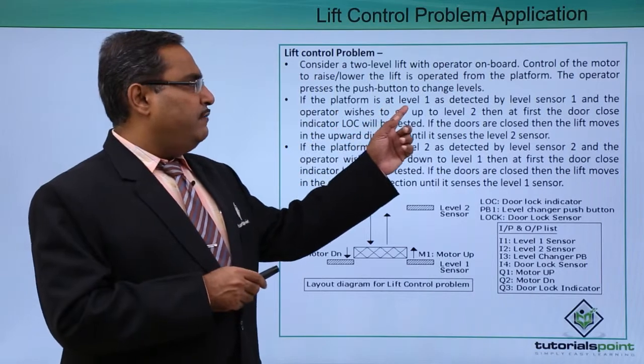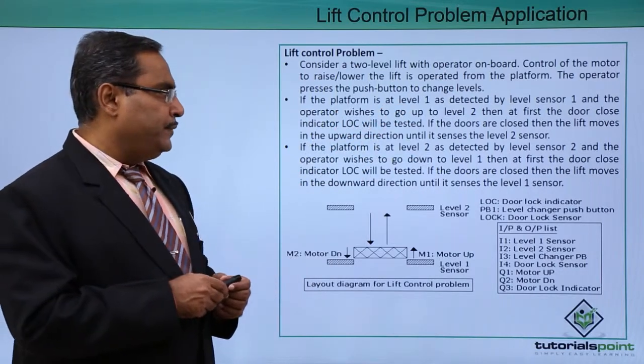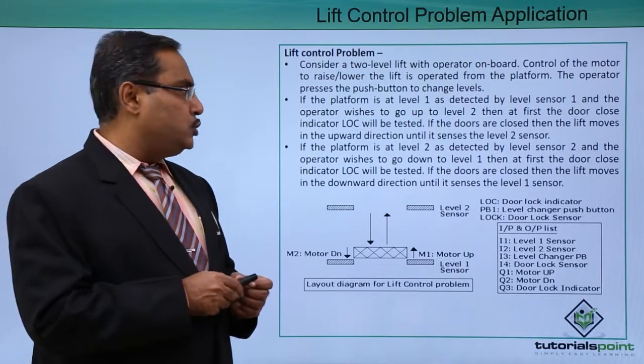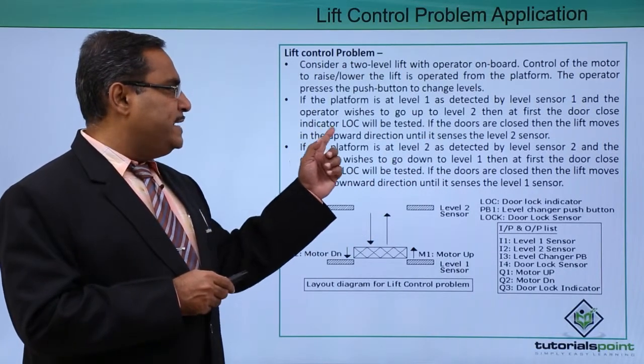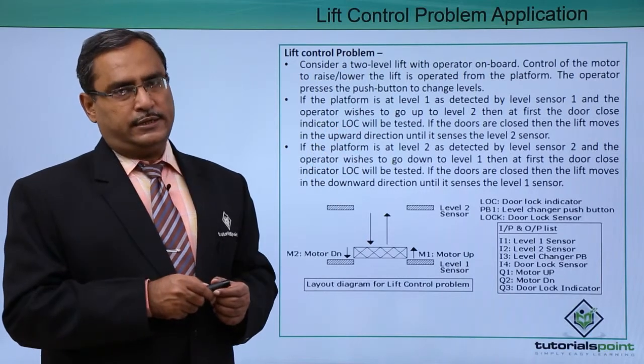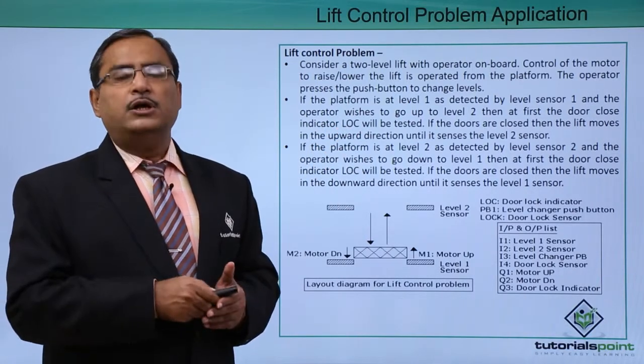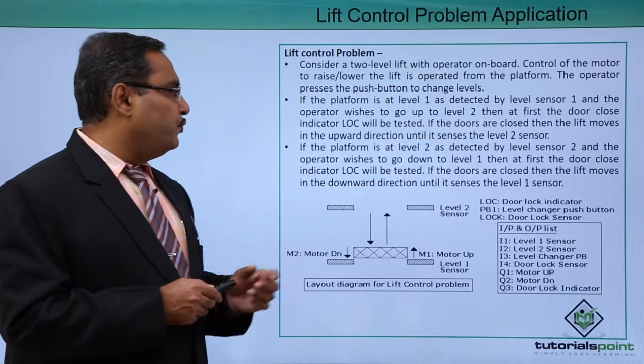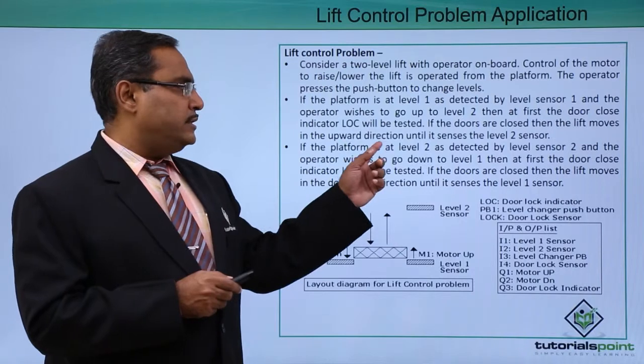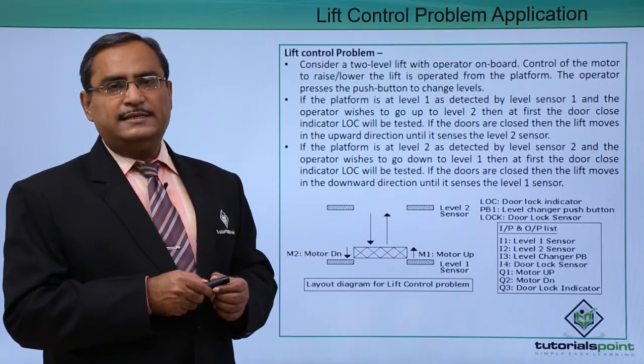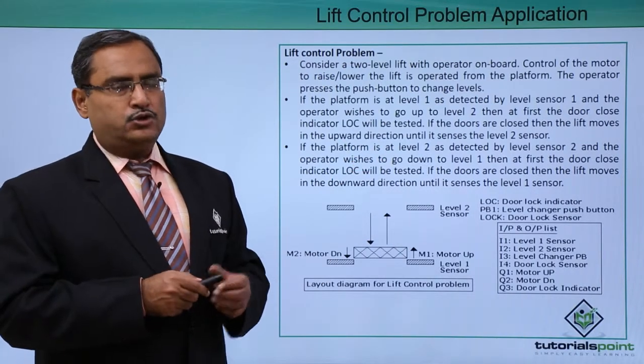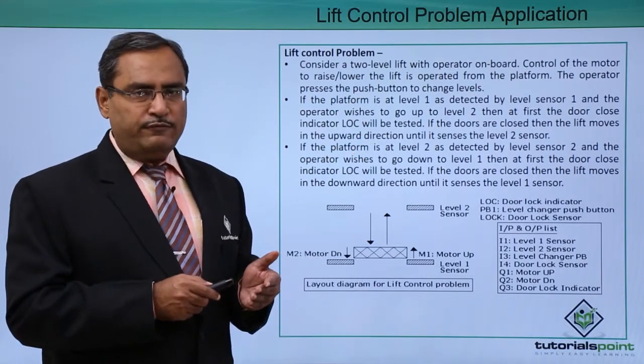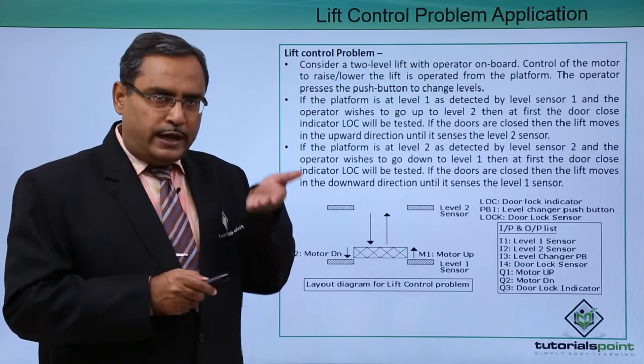If the platform is at level one, as detected by level sensor one, and the operator wishes to go up to level two, then first the door close indicator (LOC) will be tested, because a lift cannot move when the doors are open. If the doors are closed, then the lift moves in the upward direction until it is sensed by the level two sensor.